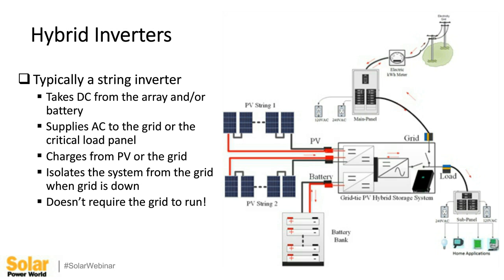Those are kind of the responsibilities of a hybrid inverter, and how it differs from a string inverter is orders of magnitude different, because a string inverter is simply: is the grid there? Yes. Is there PV? Yes. Convert power and send it to the grid. Pretty simple compared to a hybrid inverter.